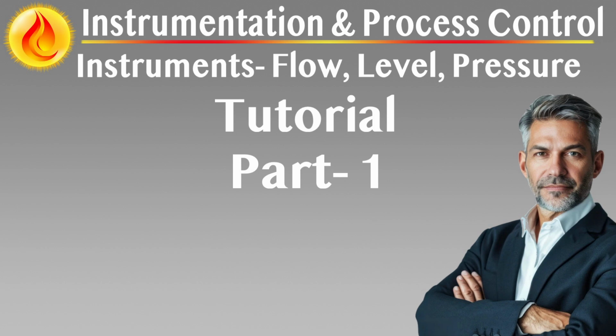Class A instruments support high-value or high-risk operations, demanding sub 0.25% accuracy for liquid flow, sub 0.5% for gas or steam, and sub 2 mm resolution for level. These are non-negotiable in fiscal transfer, reactor feed control, or emission monitoring. Class B supports process control with tolerances around 2 to 3%, while Class C and D allow for wider deviations in non-critical or trending applications.